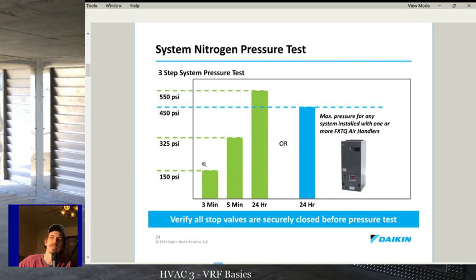Make sure you don't have any leaks. Then take the system up to whatever the test pressure is, and if the test pressure is less than 300 psi, maybe stage it a little bit, but most of our systems are 410A right now, so most of them have a test pressure of at least 450.